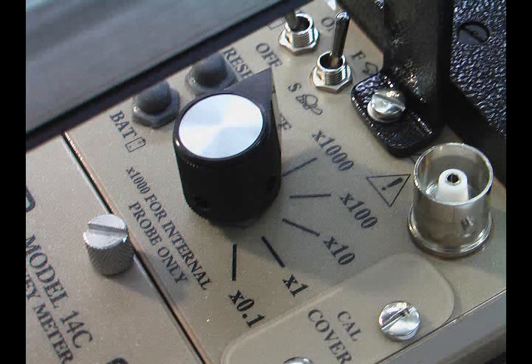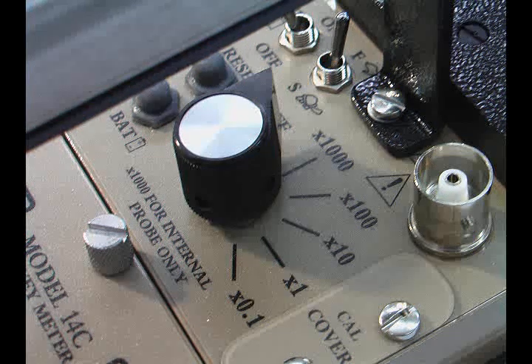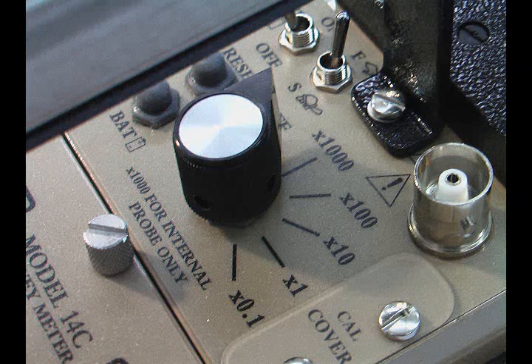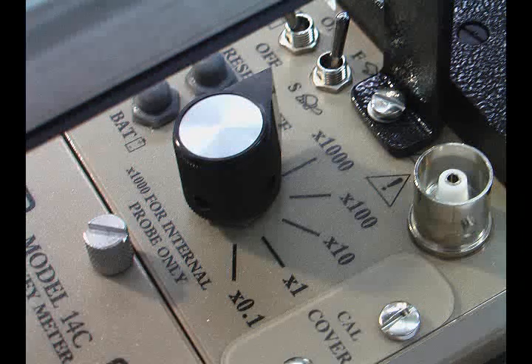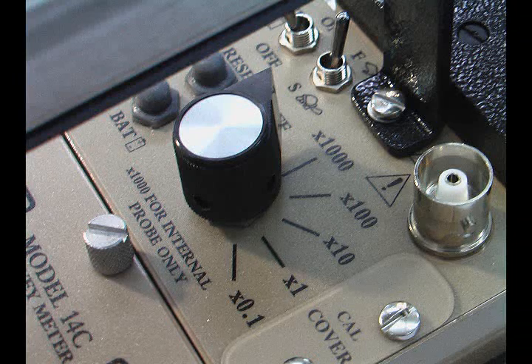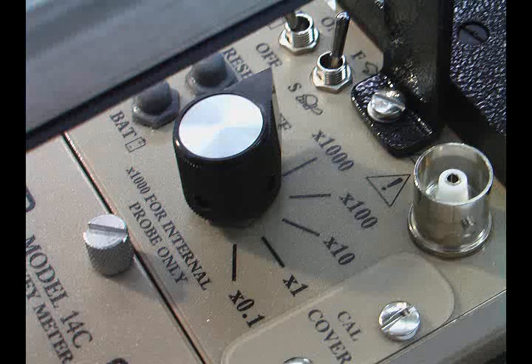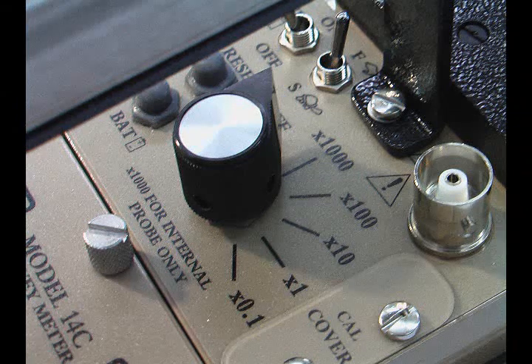The range multiplier selector switch is a 6-position switch marked off, times 1,000, times 100, times 10, times 1, and times 0.1. Moving the range selector switch to one of the range multiplier positions provides the operator with an overall range of 0 to 2,000 milliroentgen per hour. Multiply the scale reading by the multiplier for determining the actual scale reading.